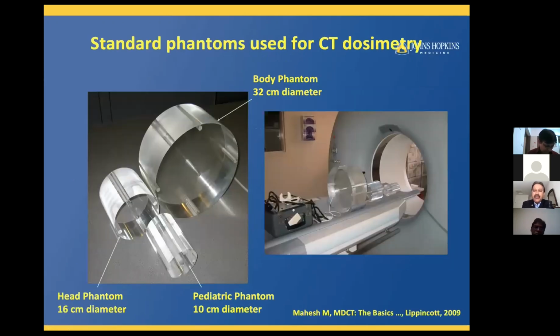These are the standard phantoms used for CT dosimetry. The large one is called the body phantom, with a 32 centimeter diameter. The small one is called a head phantom, with a 16 centimeter diameter. Sometimes we also have a pediatric phantom, which is 10 centimeters. But typically the body and head phantoms have been the standard ones used for a lot of the dose display on the scanner.